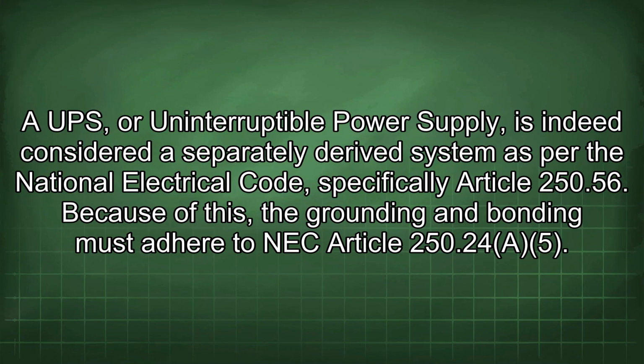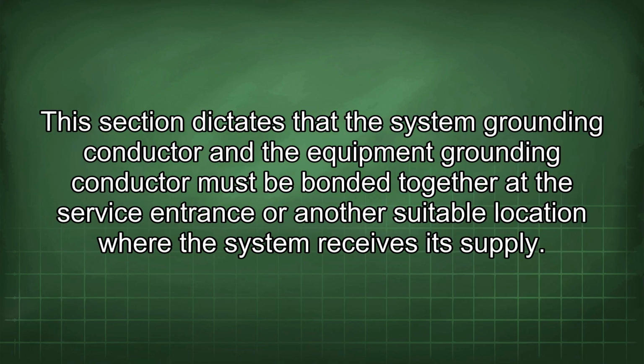UPS, or uninterruptible power supply, is indeed considered a separately derived system as per the National Electrical Code, specifically Article 250.56. Because of this, the grounding and bonding must adhere to NEC Article 250.24. This section dictates that the system grounding conductor and the equipment grounding conductor must be bonded together at the service entrance or another suitable location where the system receives its supply.